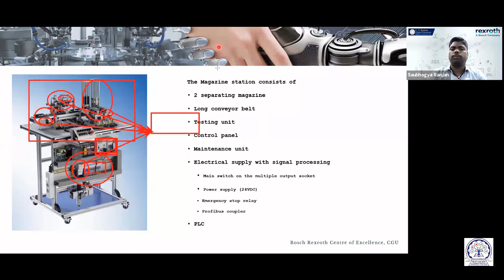So what happens there? The input output for this section, you don't need to extend the wire, so you keep it here only. Input output for this section, the IOs keep it here. Similarly, keep it here. But these are the IOs only, you can't control them, they don't have any processing power. So you need one main PLC here, and instead of individual wires, you can just take one Profibus coupler and connect that with the PLC. Like this you can connect, or you can make ring topology, bus topology, all these things also. In this way the number of wires will be reduced and the data transfer will be faster. So they are known as your Profibus modules or remote IO.